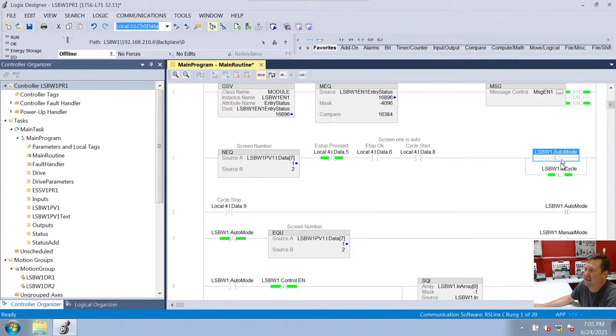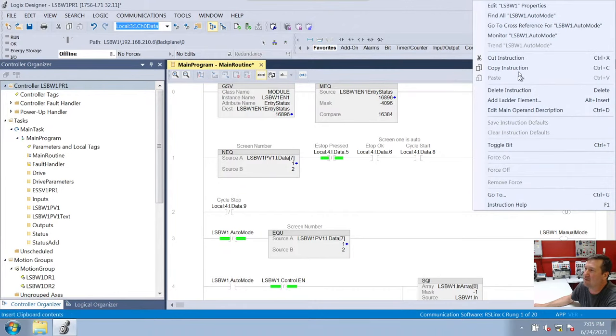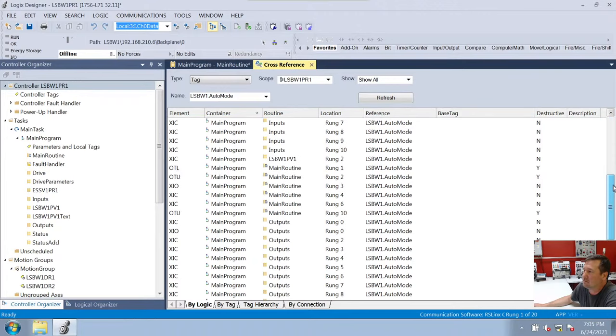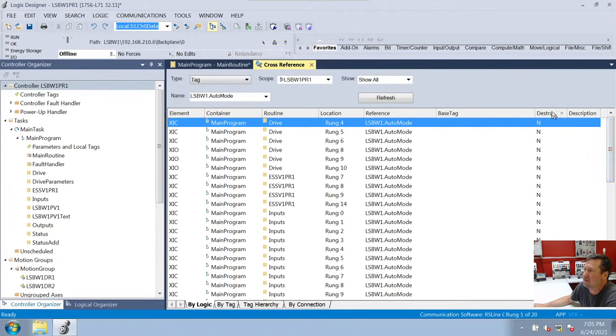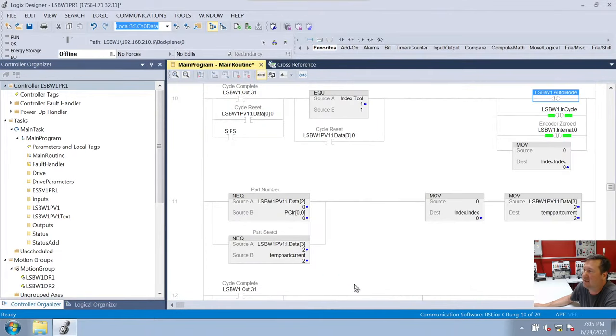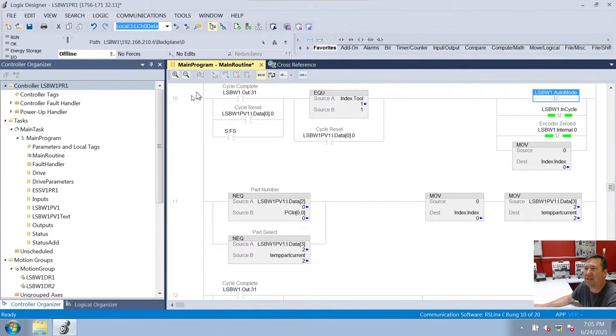Let's look at this auto mode and see how I did my latch and unlatch. I'm hoping I have a latch and an unlatch. Maybe there's a first scan bit that's unlatching. I'll cross-reference this and sort by the destructive column. We have an output latch and output unlatch. On rung 10, if cycle is complete, cycle reset, or first scan — we'll unlatch auto mode. So I would knock myself tremendously for this latch-unlatch here.